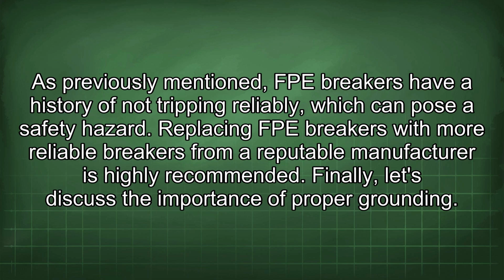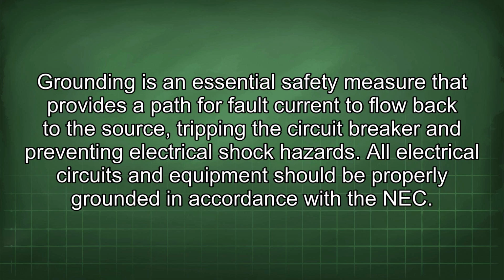As previously mentioned, FPE breakers have a history of not tripping reliably, which can pose a safety hazard. Replacing FPE breakers with more reliable breakers from a reputable manufacturer is highly recommended. Finally, let's discuss the importance of proper grounding. Grounding is an essential safety measure that provides a path for fault current to flow back to the source, tripping the circuit breaker and preventing electrical shock hazards.